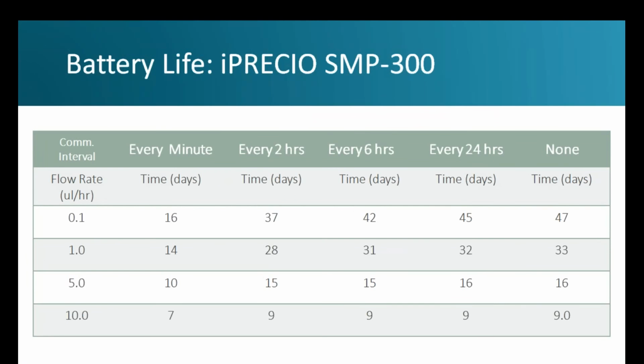The battery life on the SMP 300 pumps is not only affected by flow rate, but also by the communication interval that is selected. These pumps give you the option to program a communication interval, which is communication with the base station, and you can program that to communicate every minute, every 2 hours, every 6 hours, 24 hours, or none. In order to maximize battery life, what we recommend is to program the pump to communicate with the base station every 6 or every 24 hours for a given flow rate. At that point, the battery life is conserved the maximum, and you still get constant communication with the base station.